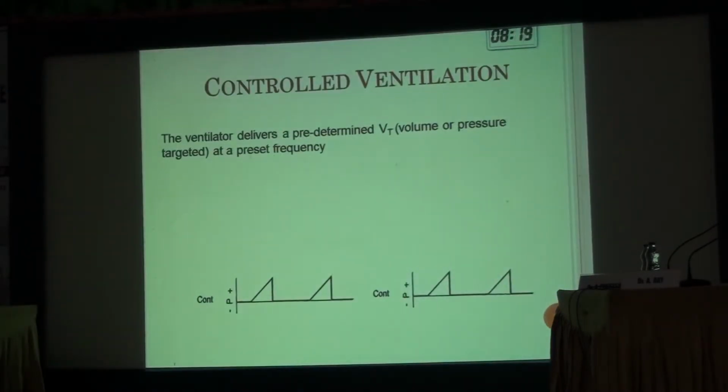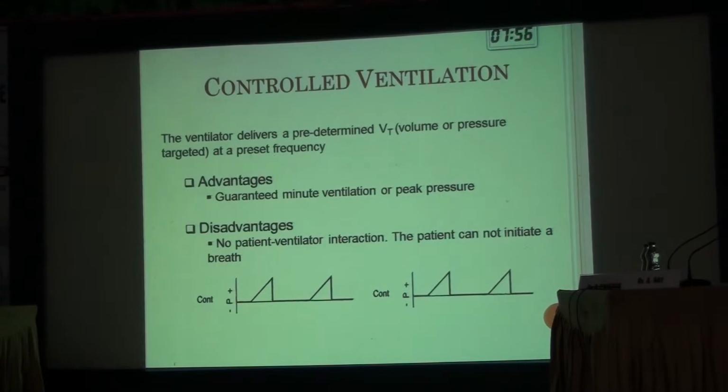Now, as I was talking to you, the different modes of ventilation, I will quickly run through this, because there are various modes, various advanced modes are also available nowadays, but it's not possible to cover everything in this short time. Control mode is something which is very common to begin with. That is the mode which we apply. The advantage is that it has got a guaranteed minute volume or the peak pressure, because whatever you set, it is going to deliver, irrespective of what the patient wants or irrespective of what the patient is trying to do.